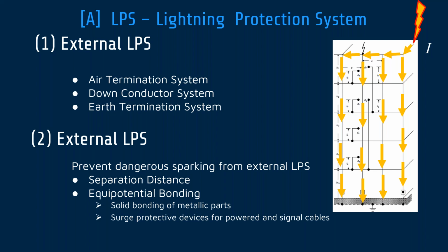So now we have the situation where the power cables can't be bonded solidly. Communications cables can't be bonded solidly. Communication cables are only an issue if I've got dangerous sparking as far as the internal LPS component is concerned. So when we implement surge protection, it's because it's a cable that carries signal, it's because we can't do anything else.